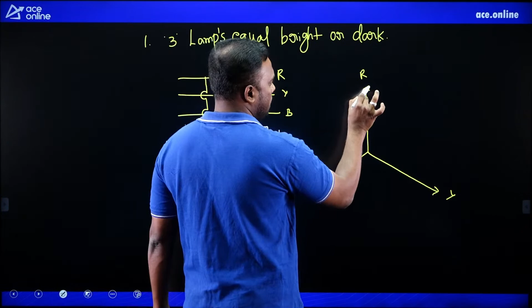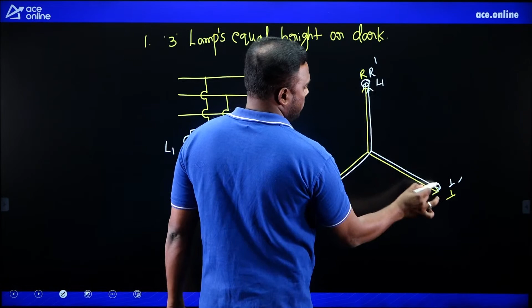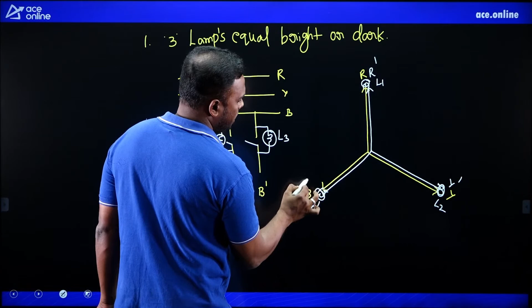At this instant the phases are present like this. Whenever we connect the lamps, R dash, Y dash, B dash are exactly in phase with bus bar R, Y, B. So the alternator's 3 phases are also in phase with the bus bar at that time, and the lamps are connected then. So this is L1, L2, L3, three lamps connected like this.